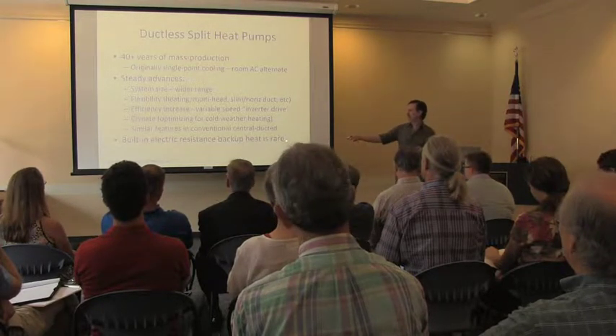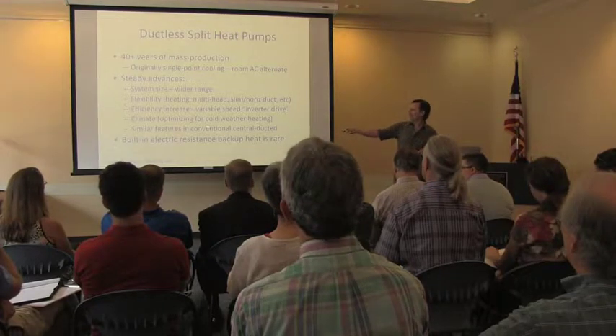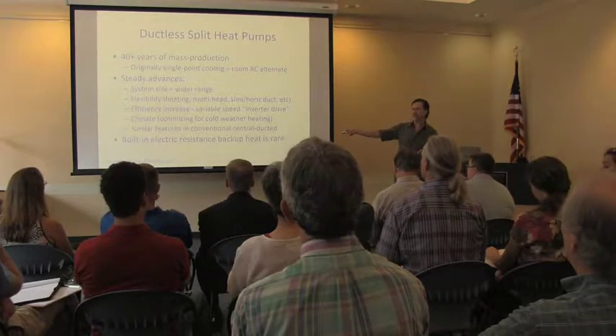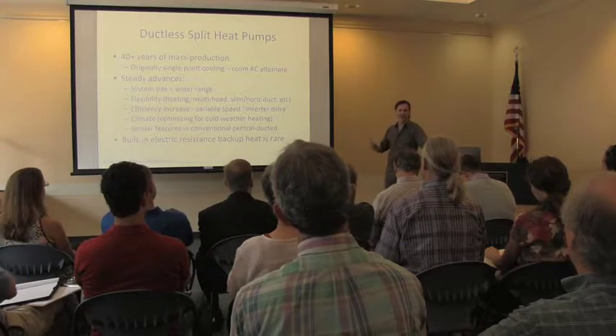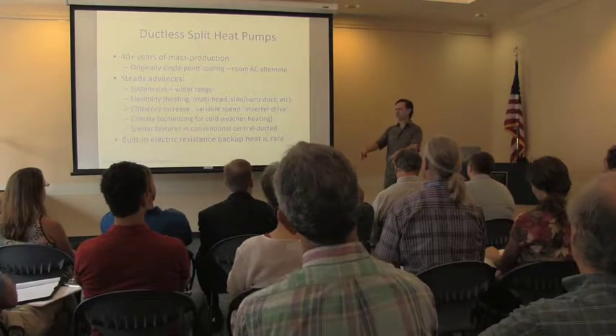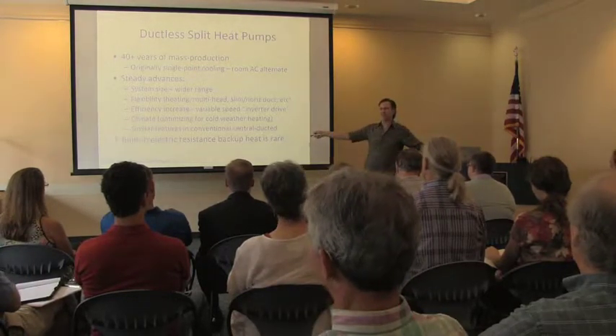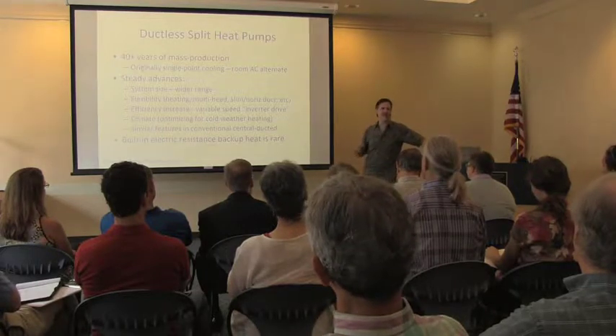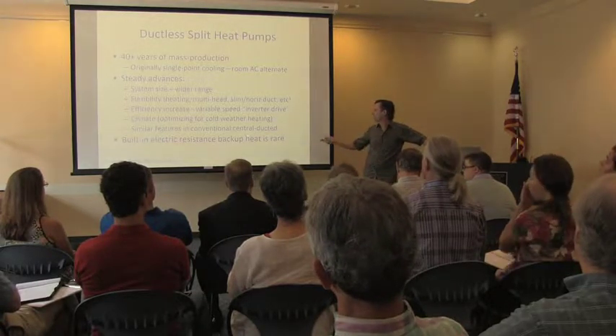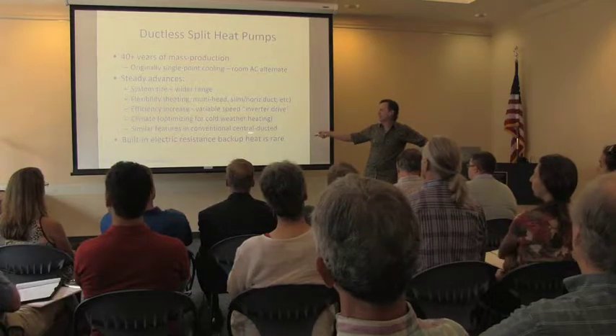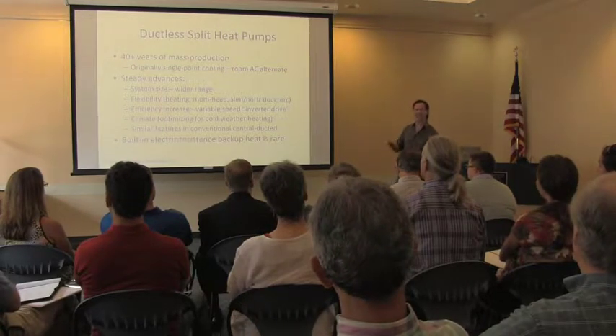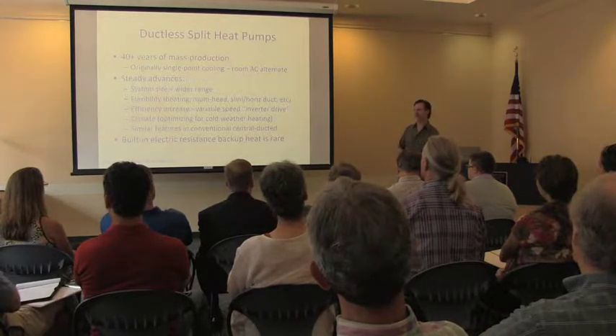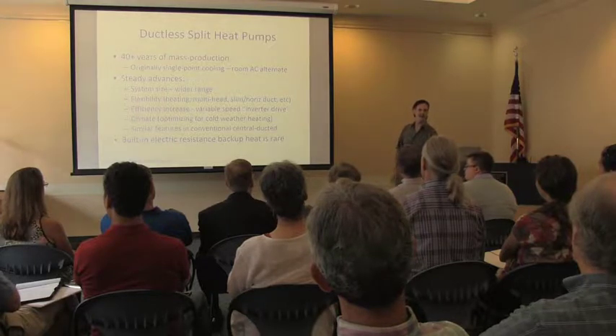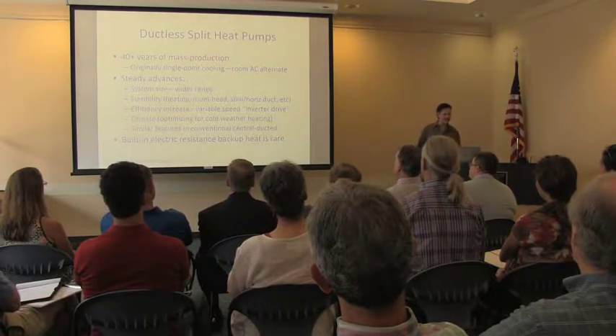The backup electric resistance heat is rare. Some of the more conventional systems, and we are seeing these cold climate air source heat pumps also in a sort of central ducted system that you would see in a lot of houses replacing a furnace or replacing an older heat pump. Those are more likely to have the electric backup heat, but if you size them properly, you really don't need that because you do have those higher capacities at cold temperatures.